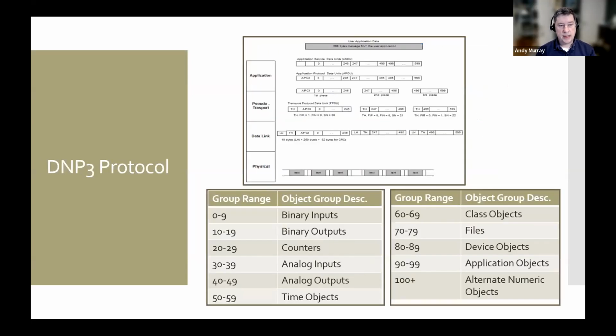The other very common protocol, and I would say this protocol now is probably the most common in the electric industry, more so than Modbus, is DNP3. Also a pretty mature protocol, but built a little more robustly than Modbus, with a lot more features in it, though still initially built for serial links, most often a 9600 baud link or higher. It also has the TCP method, so you can do DNP over TCP, and that's probably most of what I see, but it's set up very similarly.